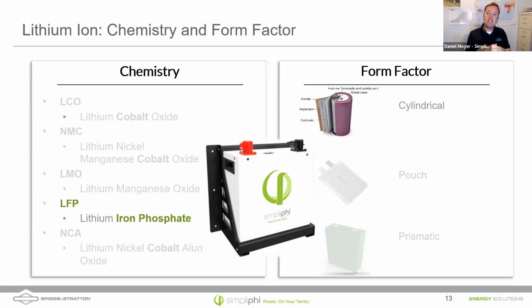There's a little vent on the top that allows it to vent out. Pouch cells are prone to puncture and swelling. Prismatic cells don't have too much wrong with them, but they do tend to have a larger cell volume, so when there's a thermal event, you get more gassing, which can be flammable. They also can swell and contract. Cylindrical cells are the safest, although they're the most expensive to manufacture.